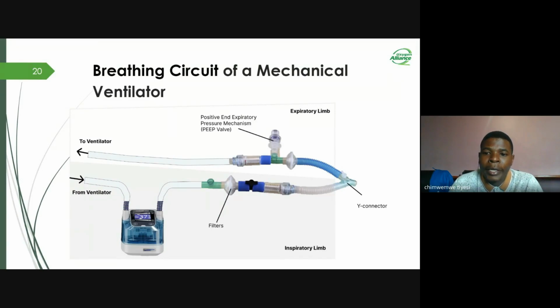On the other hand, the expiratory limb facilitates the exit of the exhaled gas from the patient. This limb is equipped with an expiratory valve, which regulates the flow of air out of the system. In cases where a positive end expiratory pressure mechanism is used, the PEEP valve, the expiratory valve may partially close during exhalation while maintaining a positive pressure in the patient's lungs to prevent alveoli collapse.